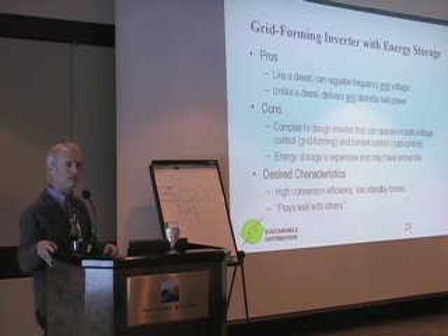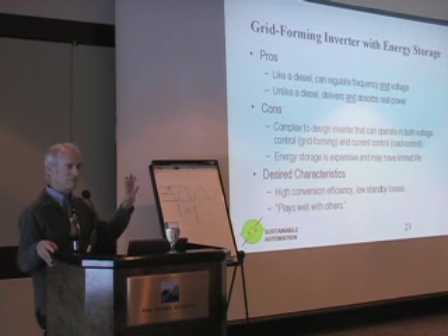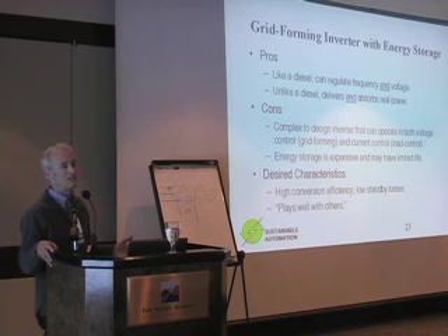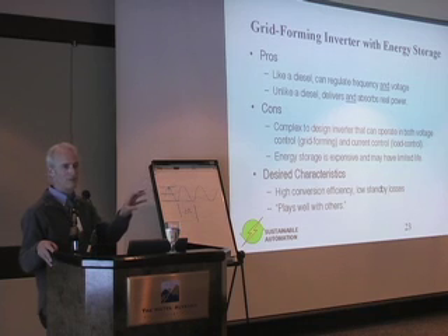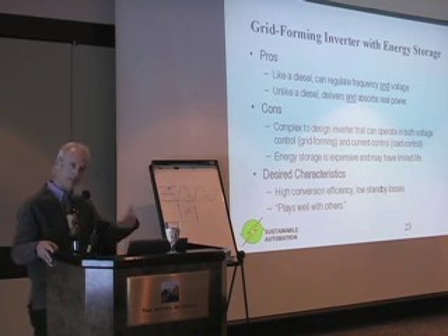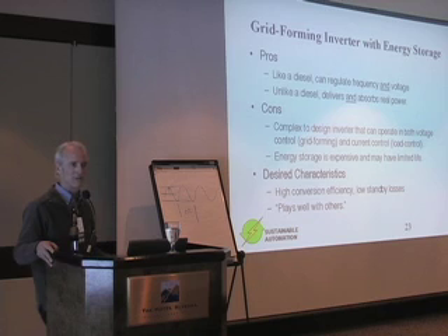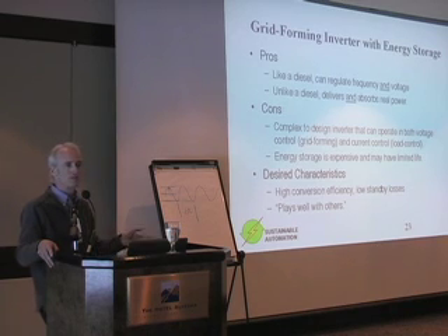So one minute you can have a genset connected to the grid just in base load mode. This is a large utility grid I'm talking about. So it can't control voltage and frequency at that point because the grid would overwhelm it. But it can feed in power, maybe in a cogen situation or something like that. And if the utility goes down, it can immediately switch over to grid forming mode or voltage control mode, and it does that relatively gracefully.